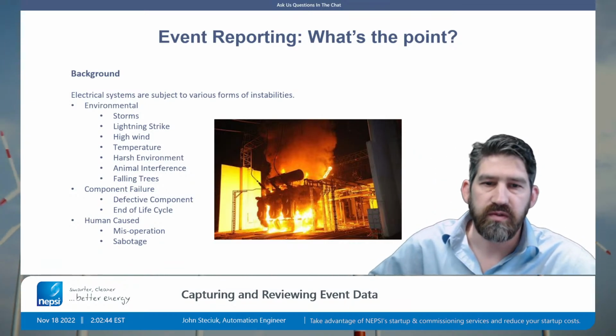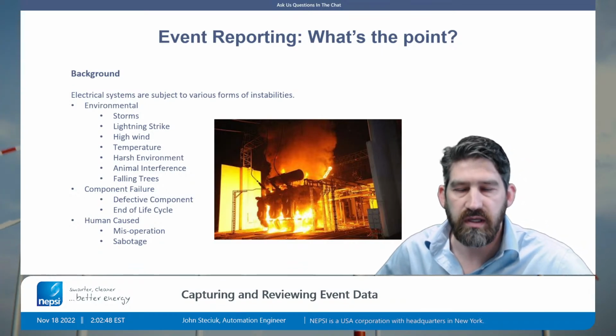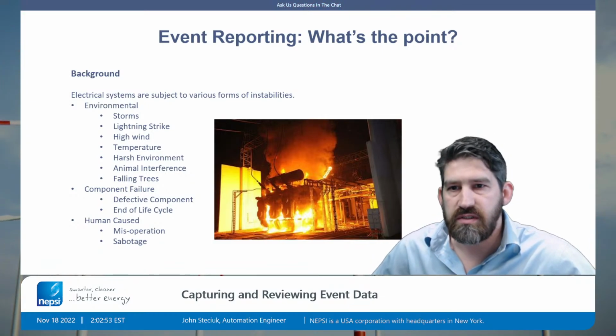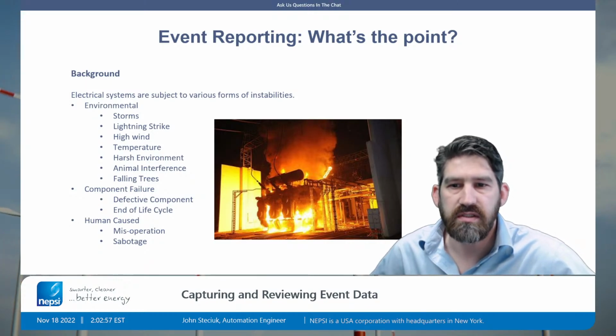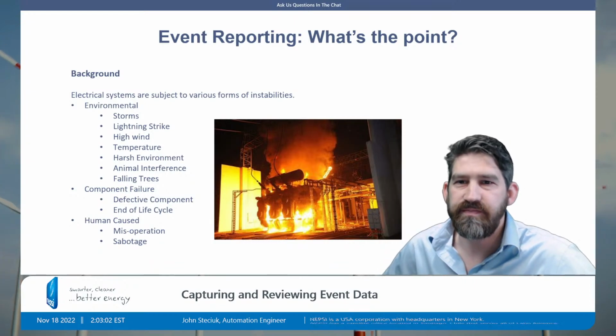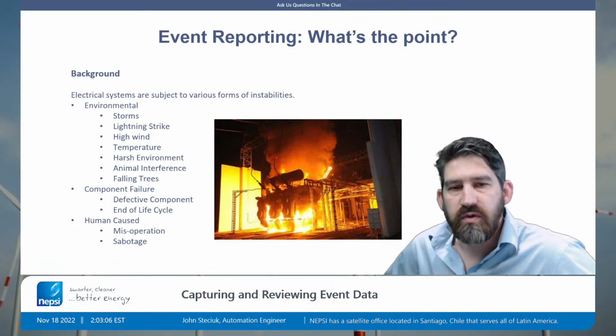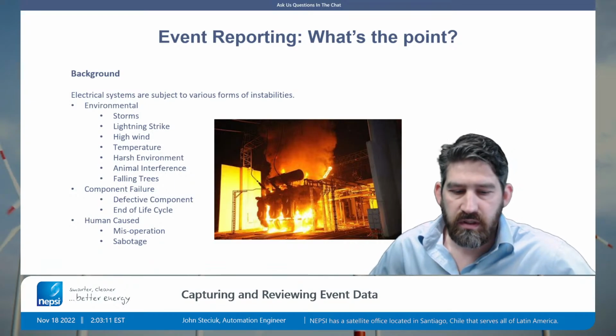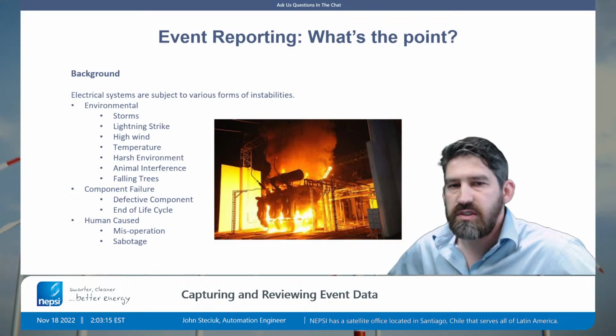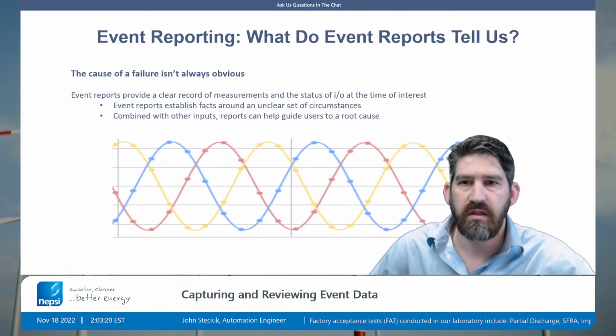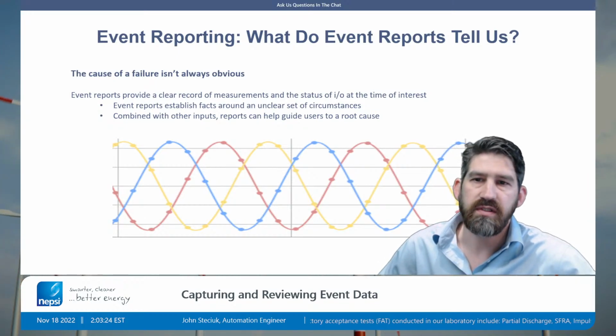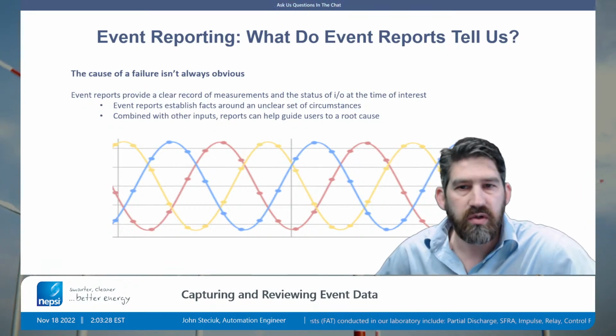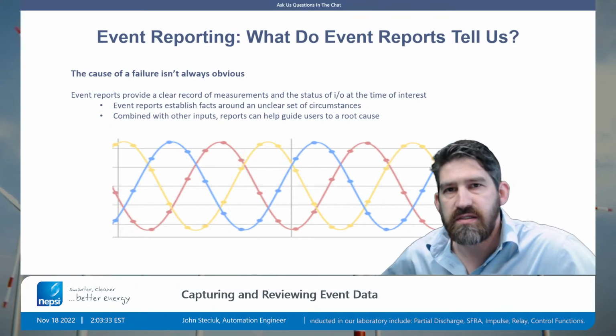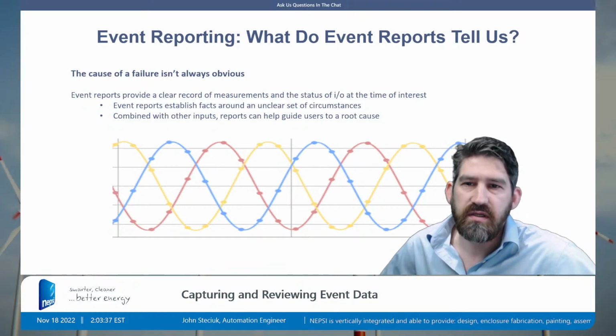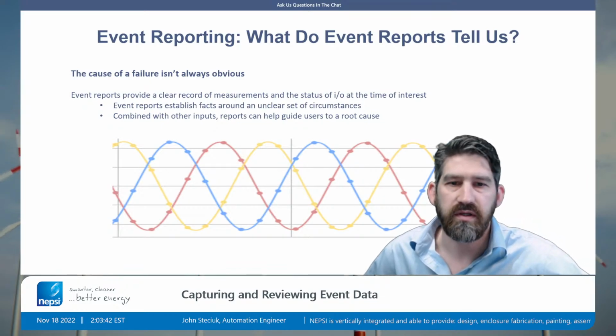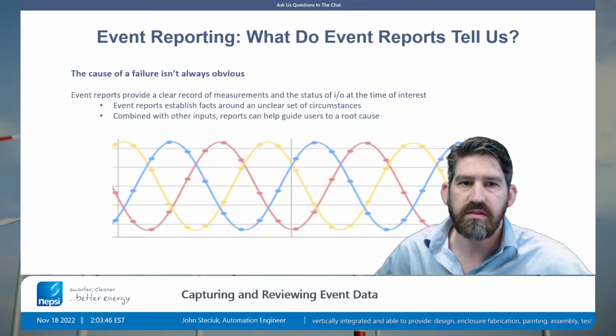Some of the ways that people are doing that now are with routine maintenance and changing out old parts, but you can't always foresee a failure, especially if you have some kind of environmental factor like storms, lightning strikes, animal interference, things of that nature. You can have human error, misoperation of equipment that results in failures, and so event reporting is going to help us answer the question, how did this happen? And the cause of the failure, even with event reporting, isn't always obvious, but the benefit is that event reports provide a clear record of measurements and the status of inputs and outputs at the time of interest. So if you combine that with other factors surrounding the failure, then it might help guide the user to the root cause of the failure.